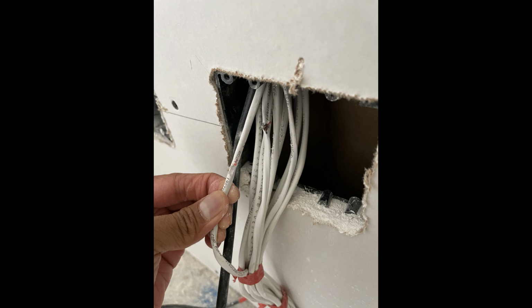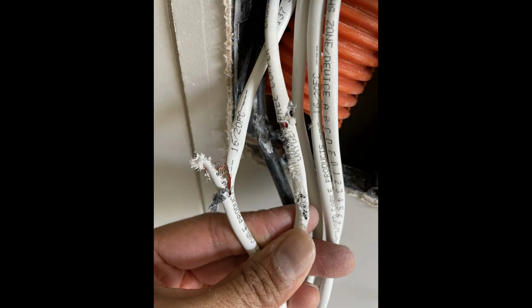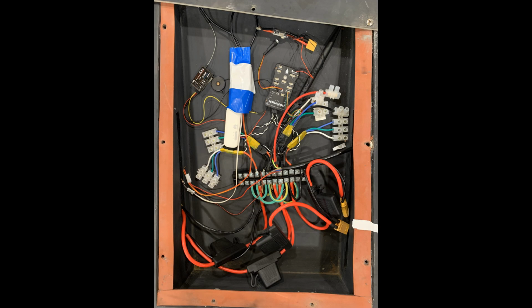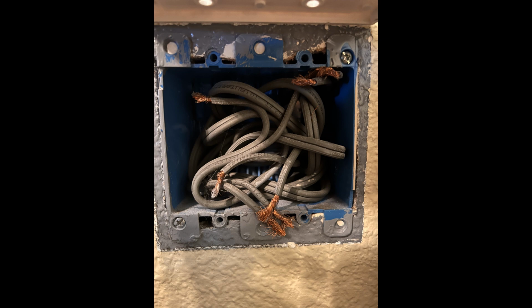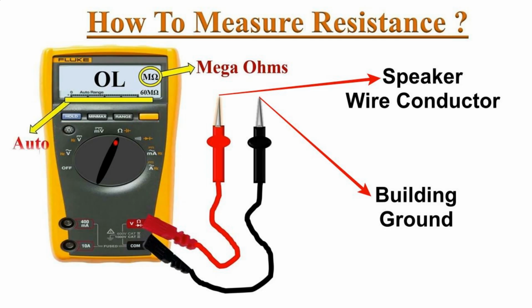This photo is an example of how wiring can be damaged through excessive force on a wire pull. Another way ground faults can occur is a poorly terminated cable with a few strands of copper touching the speaker or metal enclosure or flex conduit. Using your voltmeter in the ohms mode, verify each speaker wire conductor has no continuity to electrical building ground.